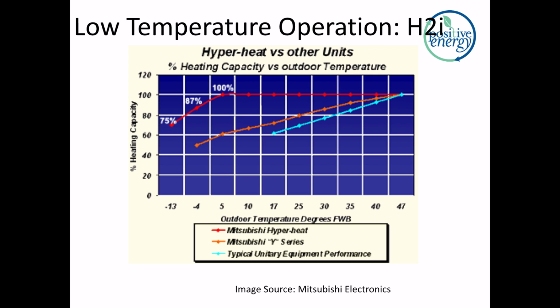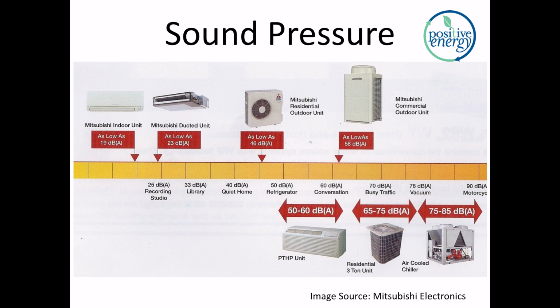Let's look at Mitsubishi as an example here. You can see they have what they call their Hyper-Heat inverter, the Hyper-Heat inverter H2i, compared to standard equipment or compared to their own non-Hyper-Heat equipment. You can see you're getting into the low single digits in terms of degrees Fahrenheit before you have roll-off in delivered capacity. That's really exciting. Even in a hot, humid climate zone, there are possible applications for extended heating performance, specifically where you see lots of glazing, lots of walls of glazing. This can cause disproportionate heating loads over cooling loads because of the higher delta T's. So if you don't want to add supplemental heat, you're going to need to possibly look at one of these units. We talked about these units being very quiet, and here's an example.